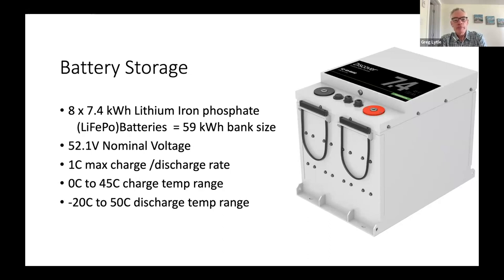One of the considerations with lithium iron phosphate batteries, as opposed to lead acid, is the temperature operating range. Here the limiting factor is the charge temperature for the battery system, which is 0 to 45. In our case, this isn't an issue because we've got them in a heated shop space, and we can maintain a reasonable 15 to 20 C range for the battery environment. But that's a consideration if you want to run your system where you don't have any way of moderating the temperature. The discharge temperature range for these batteries is greater, but that's not really a limiting factor in our particular case.